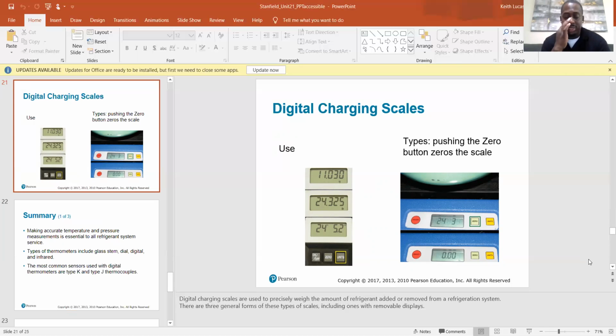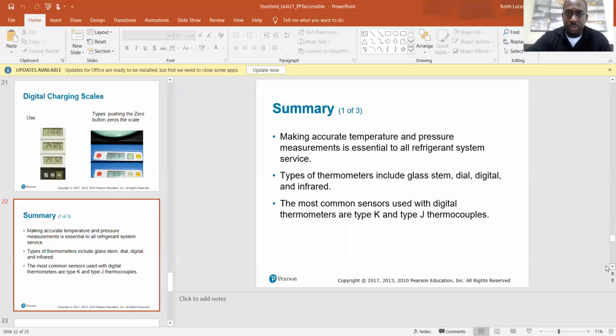But these scales are cool because they measure weight, positive and negative weight. So basically, if you're removing refrigerant from a system into a recovery tank, then that recovery tank is going to get heavier and heavier, and it's going to give you that reading. But it also reads negative measurements. So let's say you're charging refrigerant into a system. You put that cylinder on the scale, and let's say that cylinder weighs 10 pounds. As you start to charge, it's going to start losing weight, and the amount of weight that is lost is how much you put into the system. So that's how our digital charging scales work.